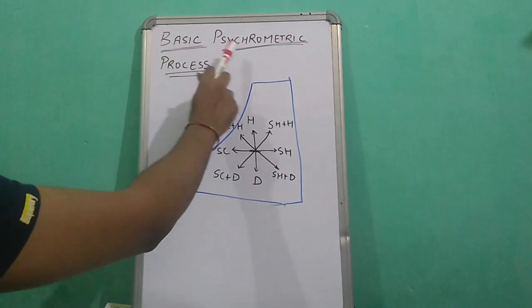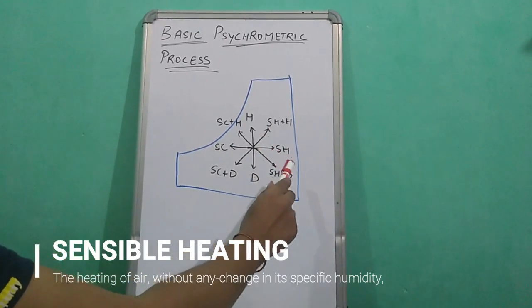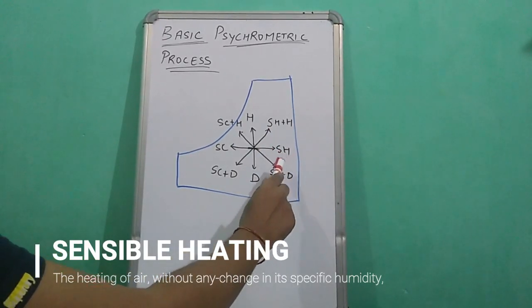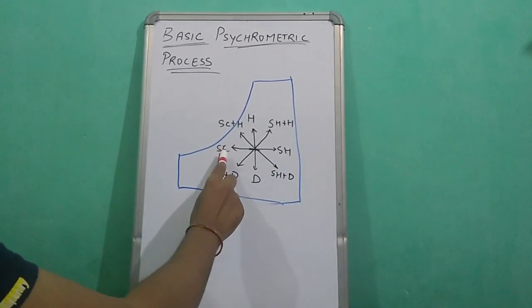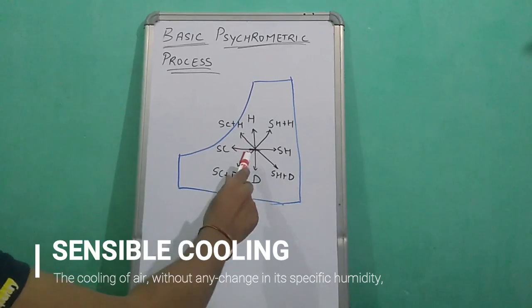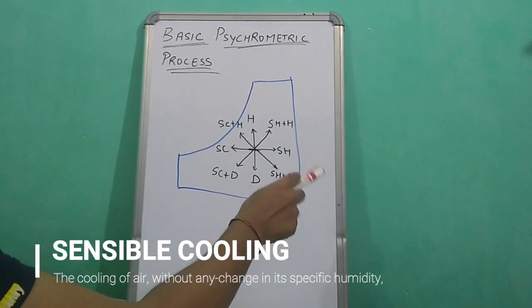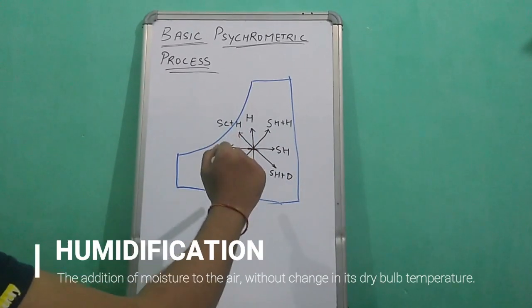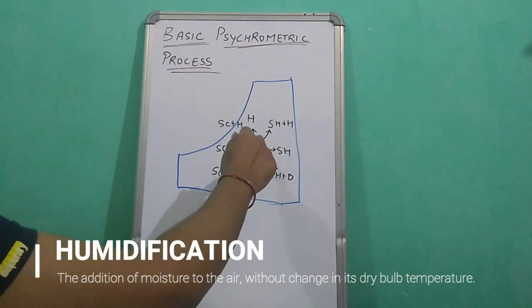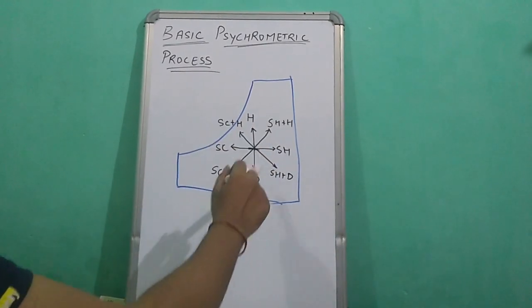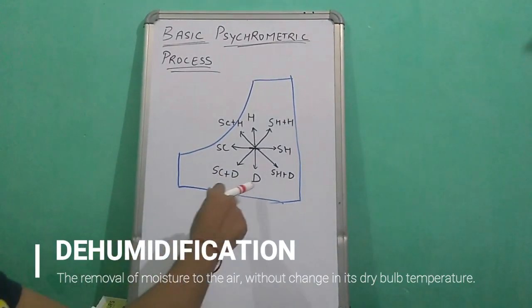Let's discuss basic psychrometric processes. First, sensible heating: it is a process of increasing dry bulb temperature at constant specific humidity. Similarly, sensible cooling is a process of decreasing dry bulb temperature at constant specific humidity. Humidification is a process of increasing specific humidity at constant dry bulb temperature. Dehumidification is a process of decreasing specific humidity at constant dry bulb temperature.